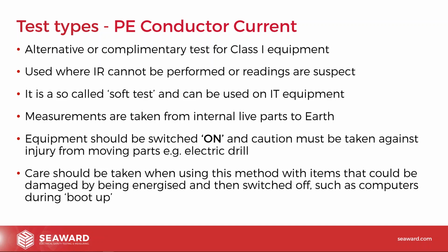It actually allows you to turn the equipment on and run it for a period of time. So from that side of things, you're getting a real world picture of it, whereas something like an insulation test will only measure so far through the equipment. And again, with an insulation test, we're using DC, not AC, so there can be differences in readings that way. So protective conductor current tests are very good, very accurate tests. Generally used, as it says there, for class 1 equipment because it's got a protective conductor. You can't do these on class 2.